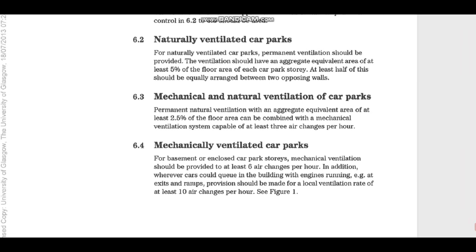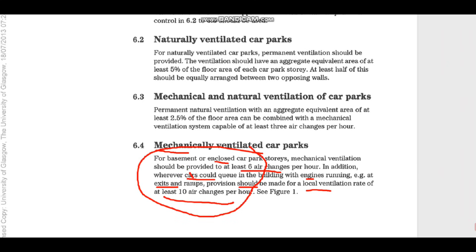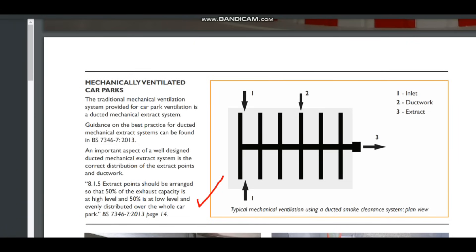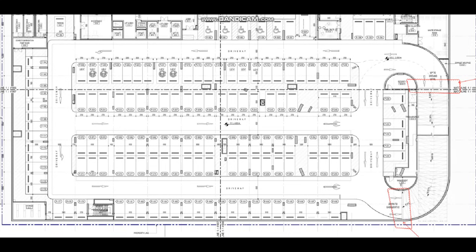Regarding air change per hour, from the same standard BS 7346: for basement or enclosed car park stories, mechanical ventilation should provide at least 6 air changes per hour. Additionally, wherever cars could queue in the building with engines running - such as at exit and ramp areas - provisions should be made for local ventilation of at least 10 air changes per hour. Most countries in the Middle East such as Qatar and UAE civil defense also recommend 6 ACH for normal mode and 10 ACH for fire mode.